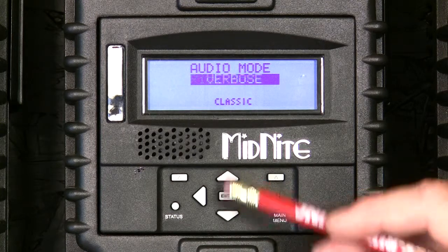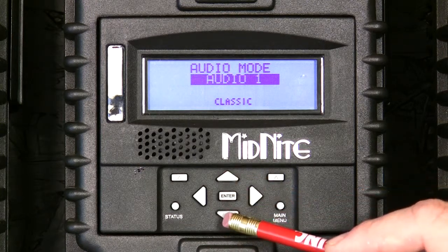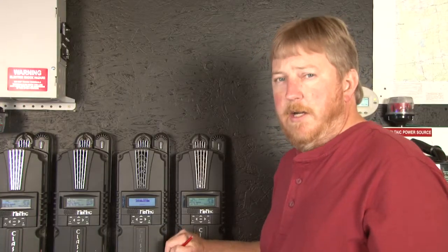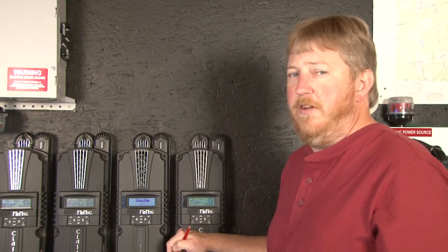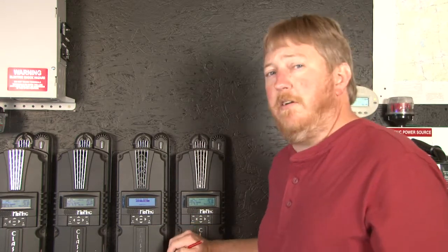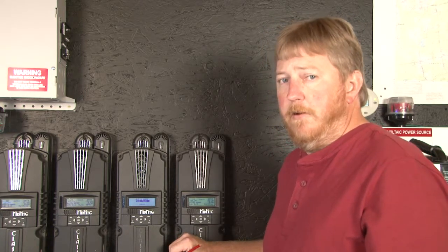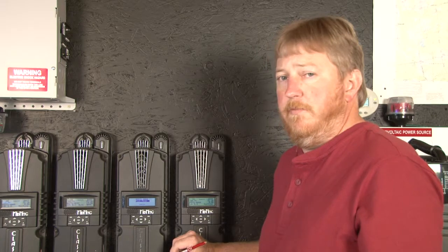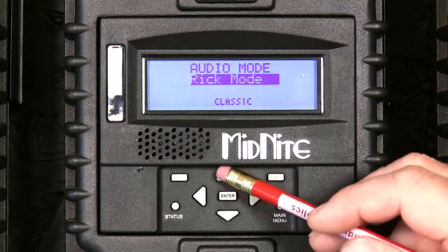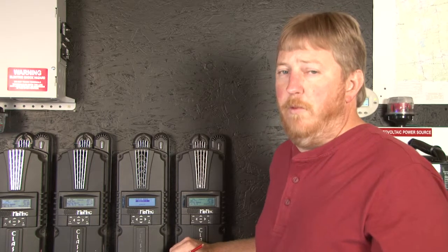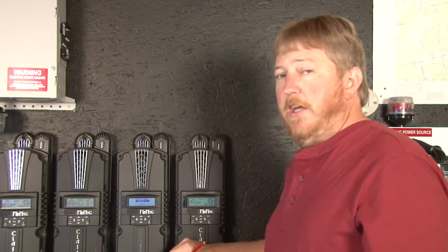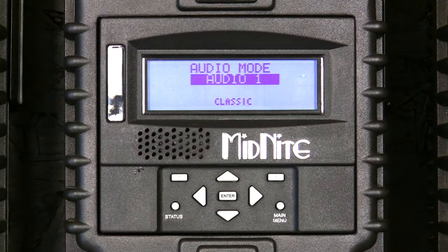Audio. Again, audio is not in the Classic yet, so some of this is not really pertaining, but as we do in the LED mode, we're going to have different modes in the audio. So if you're like Rick and you don't want your charge controller talking to you as well as not blinking to you, you can put it in Rick Mode. It's only going to tell you the fatal errors. It's going to tell you you've got an arc fault or a ground fault or over temperature, something like that. Only the fatal stuff that's dangerous. Verbose will tell you every button push. And audio 1 is going to be general stuff, you know, hey, aux 1 is on, aux 2 is on. Knowing the engineers on this project, there'll be some interesting audio in this thing.